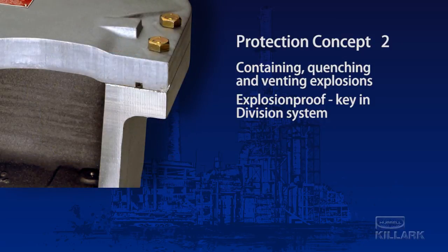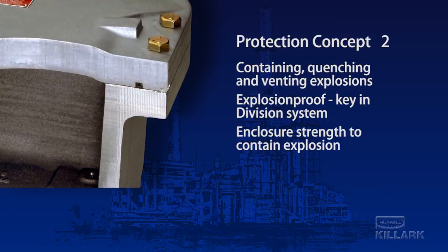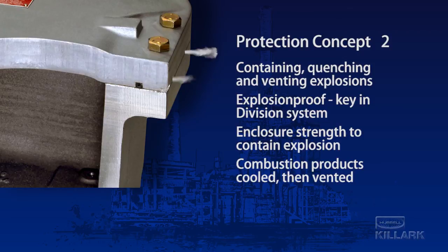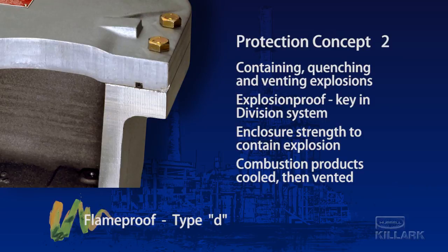The enclosures are engineered with more than sufficient strength to contain an internal explosion of a specified gas, and are then able to vent the products of combustion to relieve the pressure, but only after they've been sufficiently cooled to prevent ignition of the surrounding atmosphere. The same technique is referred to as flame-proof in the IEC system and is designated Type D.